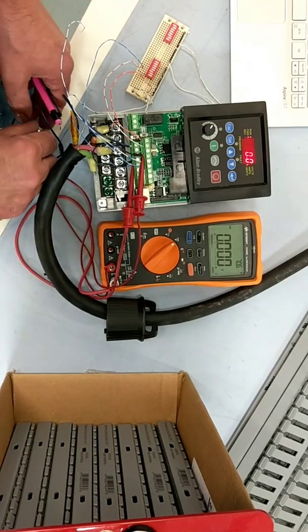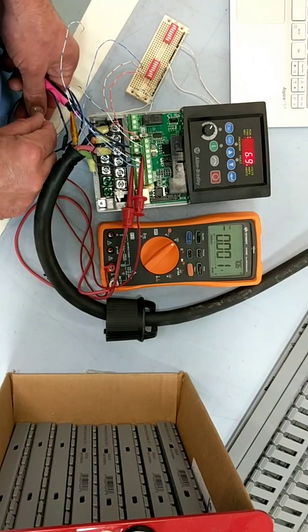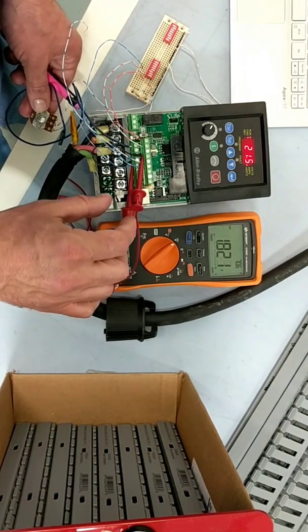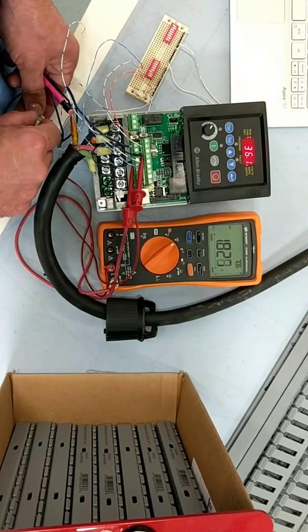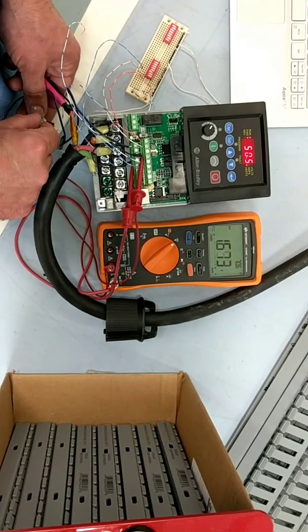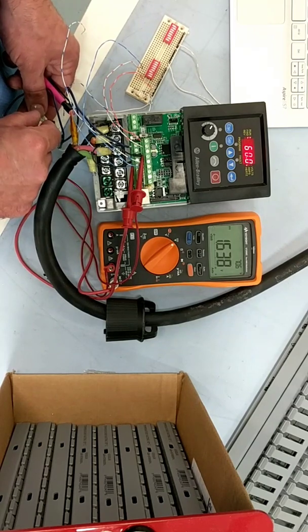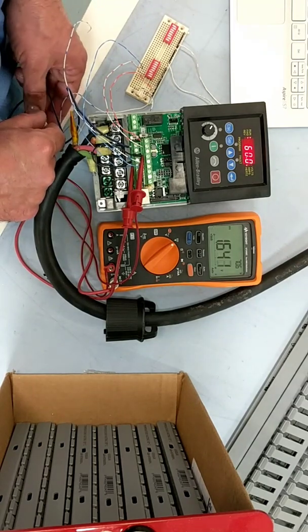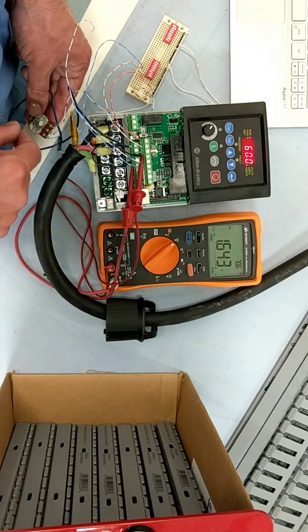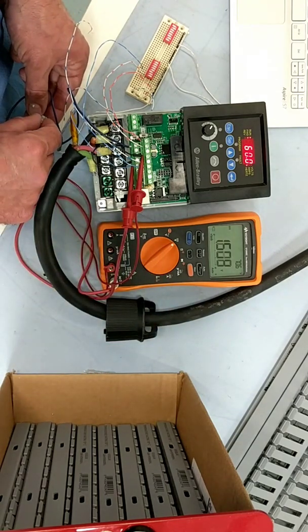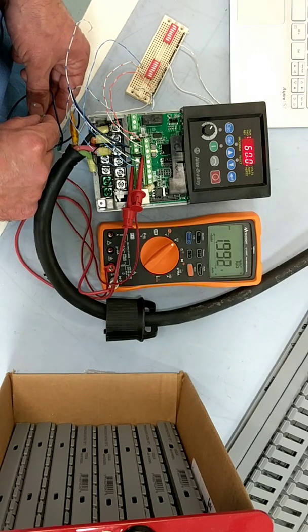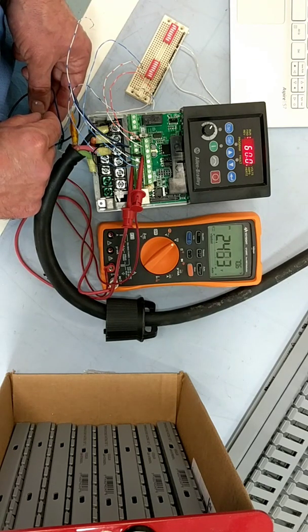And we see that's changed now. We're not seeing my voltage. There we are. Okay, so this potentiometer is changing the 4 to 20 milliamp input, and that's represented here by a 1 to 5 volt signal. So when our voltage gets to around 3.4, that's the set point. And since the drive ramped up to maximum already, 60 hertz, then we'll start to see it come back the other direction.